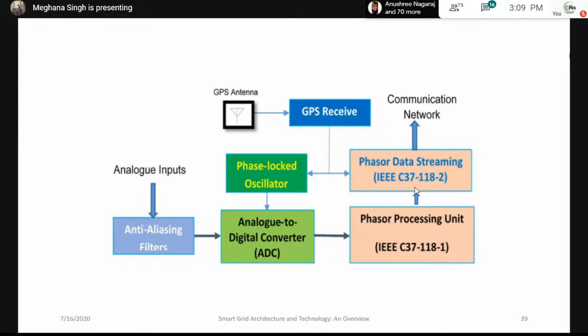Voltage and current are important; we sense them using PT and CT, pass them through anti-aliasing low pass filters, then to the ADC, then to a microprocessor. Microcontrollers or DSP processors can be used depending on your interest. Then it is given to a modem for output. There is also a GPS receiver and phase lock oscillator feeding the analog to digital converter, which is then given to the microprocessor. This is based on applying signal processing to PMUs.